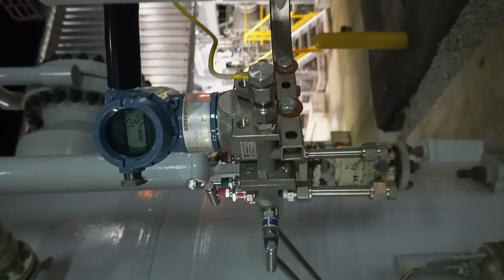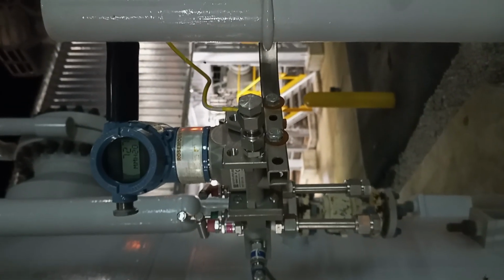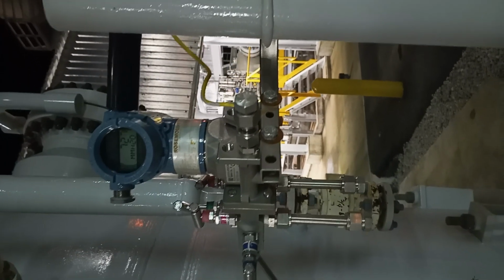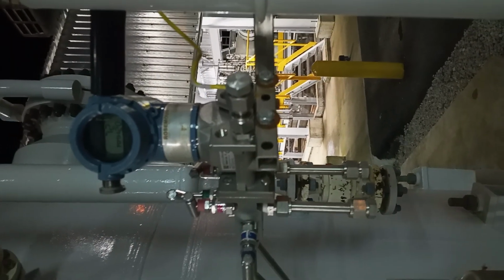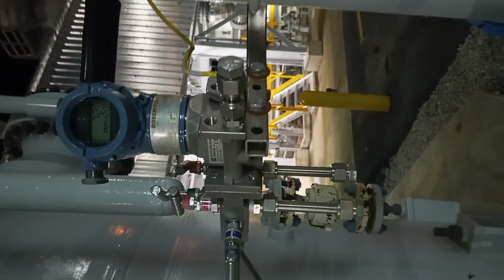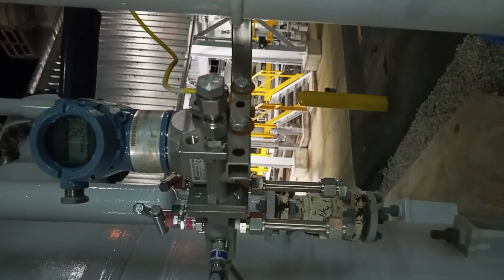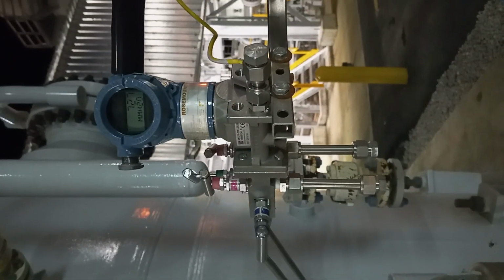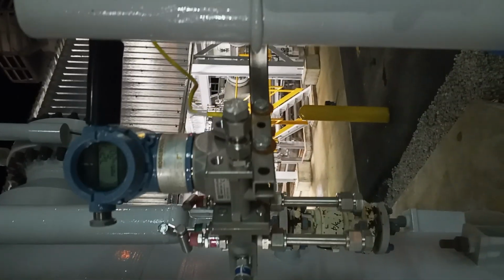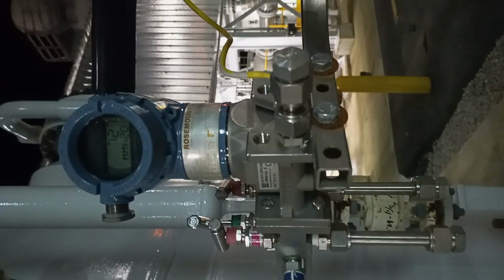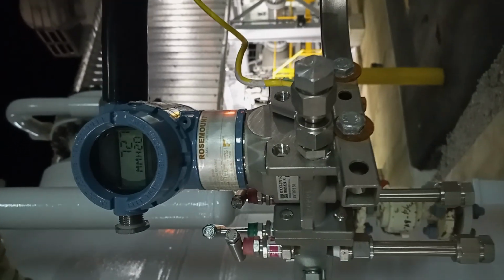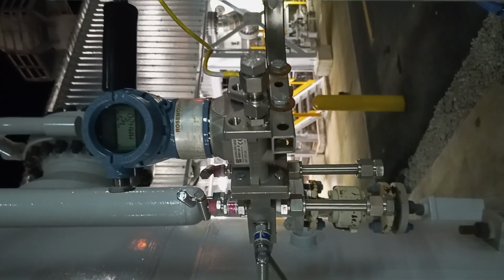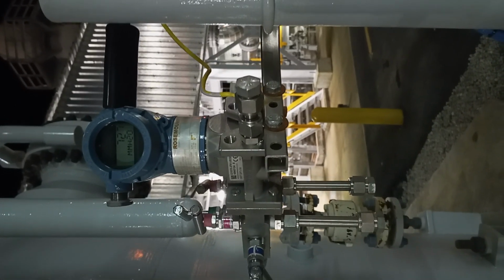Let me also mention that they can also be used to monitor pressure drop across filters. That is where you have differential pressure in the filter, to know if the filter is clogged or not. So when it is clogged, you see the pressure across the filter will increase. In our subsequent video, we will go into detailed explanation of some of these important components in the processing facility. Let us move to control equipment.